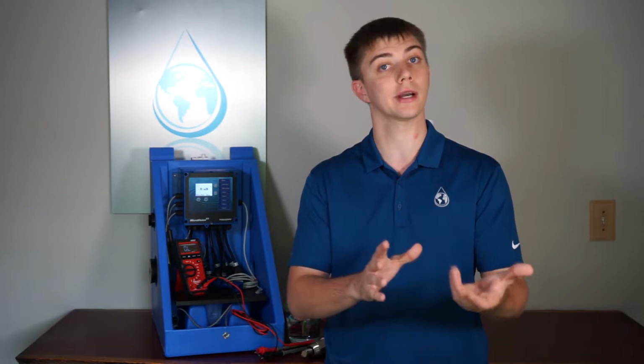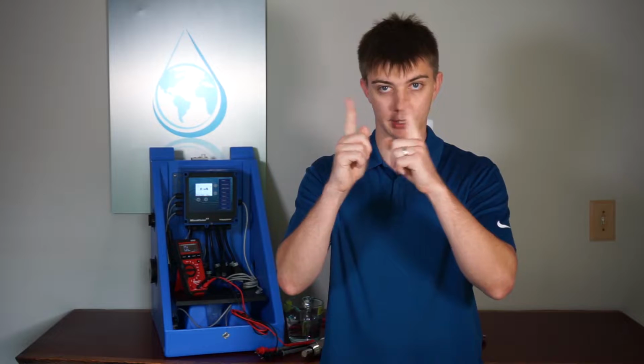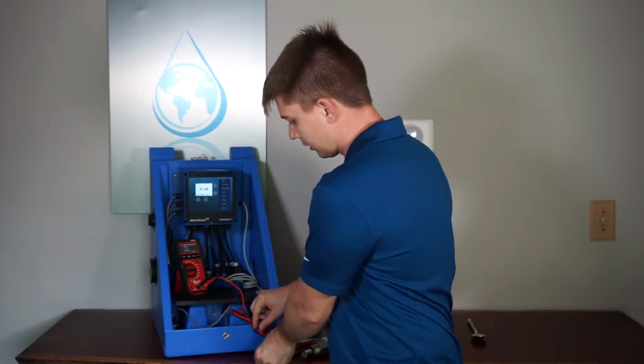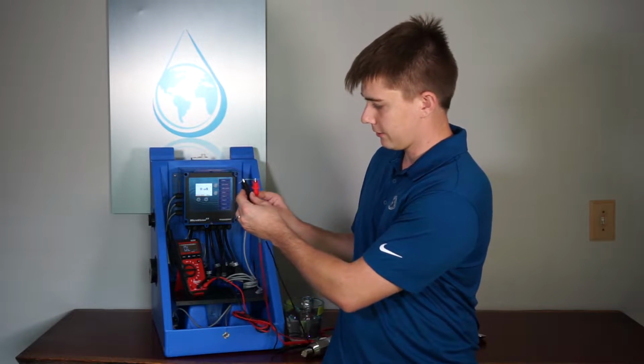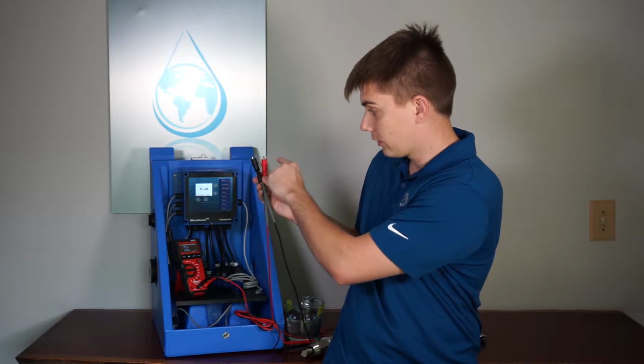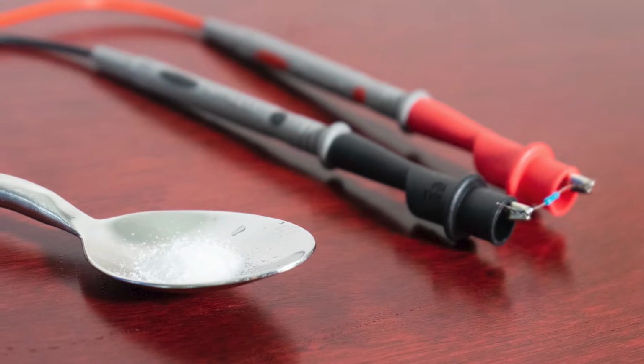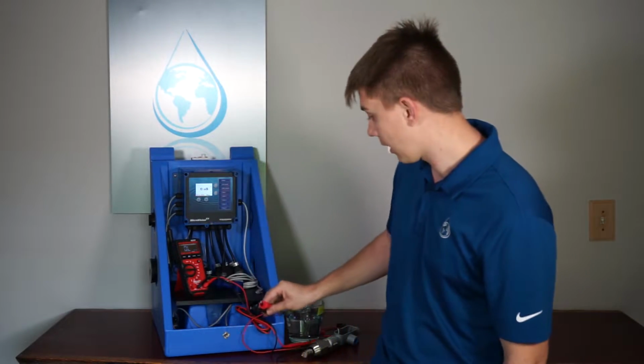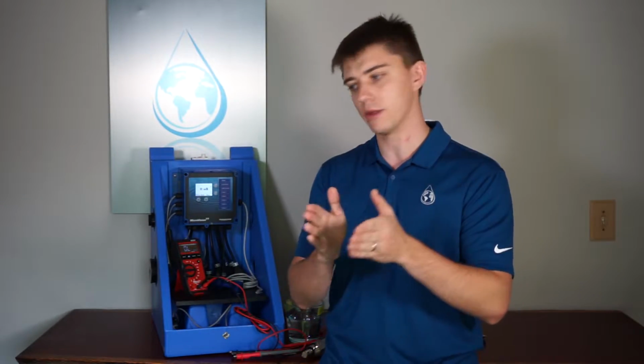Conductivity in this industry is known as microsiemens per centimeter. Microsiemens is the inverse of resistance, or how conductive something is, per centimeter is basically for every centimeter. So I'm thinking about a standard conductivity probe. It works a lot like a multimeter. With a multimeter, you have a positive and a negative, you've got a predefined distance, and you're measuring resistance.